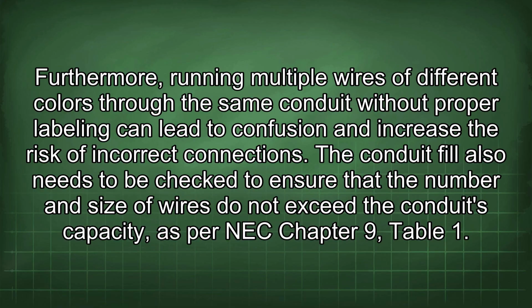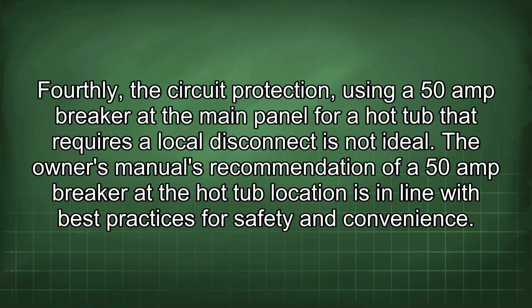The conduit fill also needs to be checked to ensure that the number and size of wires do not exceed the conduit's capacity, as per NEC Chapter 9, Table 1. Fourthly, the circuit protection. Using a 50 amp breaker at the main panel for a hot tub that requires a local disconnect is not ideal.